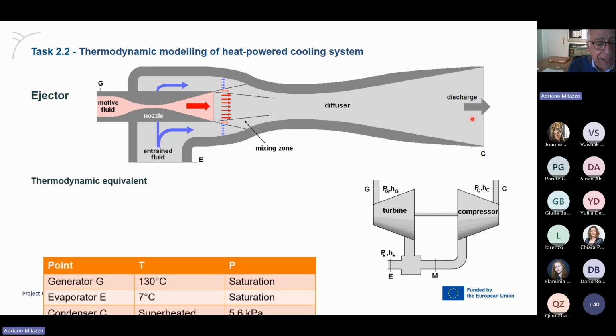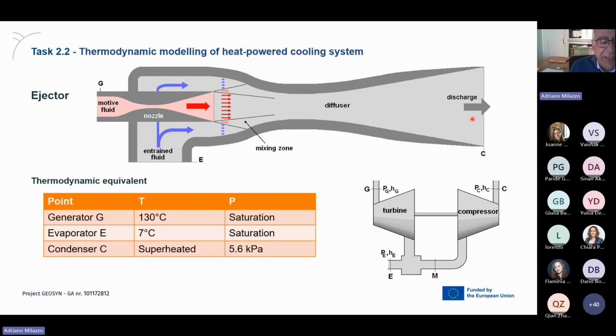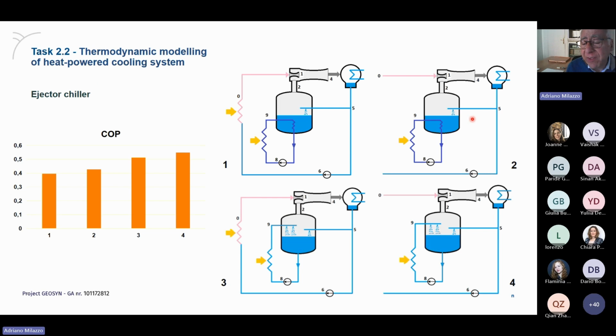If we model a simple device like this, we would end up with a COP of 1.3. That is the ratio between the useful effect, the cooling, and the energy which is given to the machine in order to produce this useful effect. We have explored again several configurations, and the COP which we get with an ejector is obviously lower. It goes between 0.40 and something more than 0.55, according to the configuration.